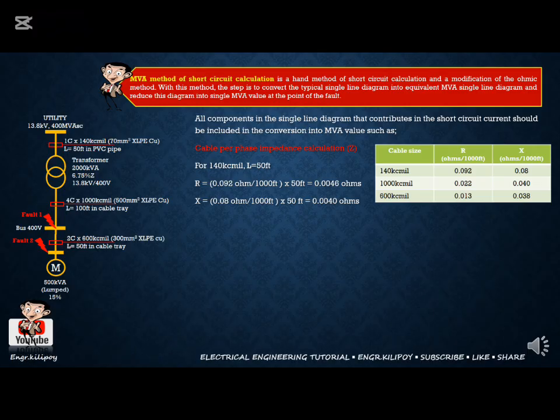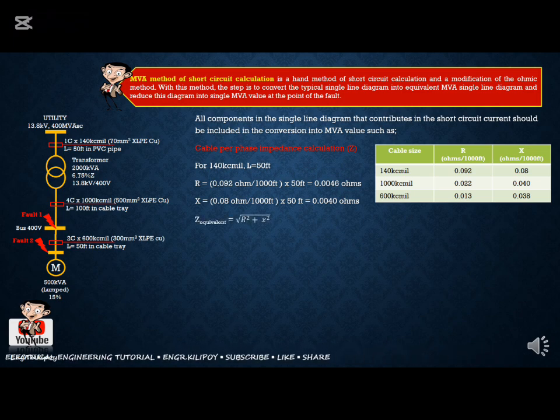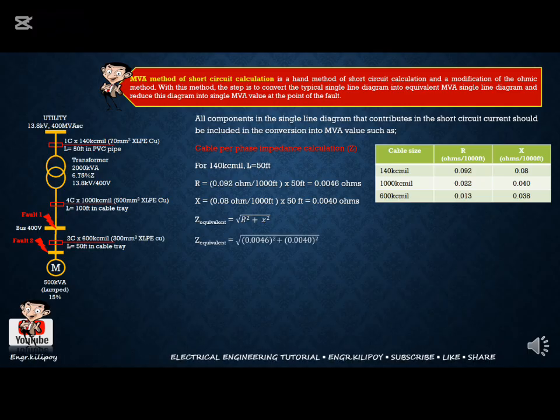So bali, obtain mo lang yung typical value ng resistance at reactance, i-multiply mo lang siya sa length ng cable, makakakuha ka na ng resistance and reactance value per cable. Hindi pa dito kasama yung number of parallel conductors. So kailangan mong kuhanin yung Z equivalent or yung impedance per cable. So simply square root of R squared plus X squared.